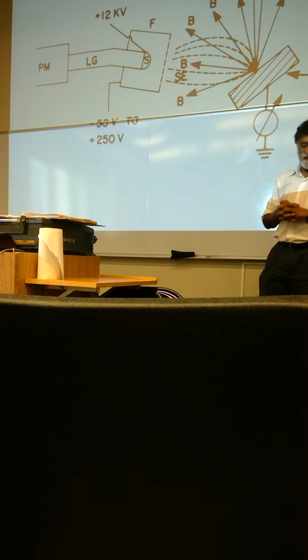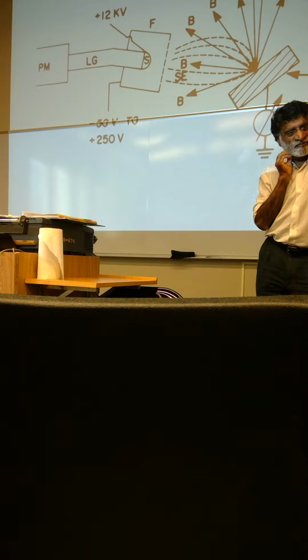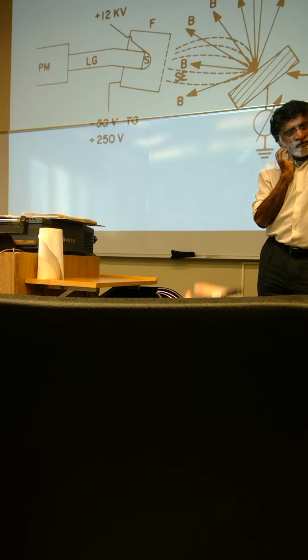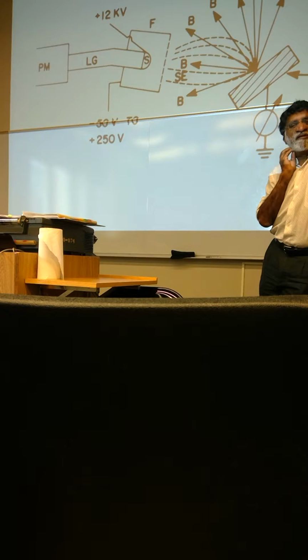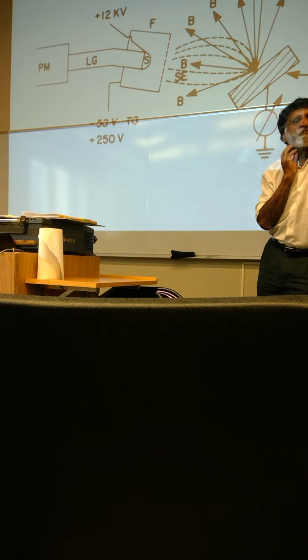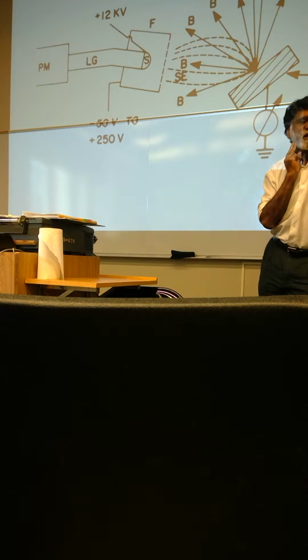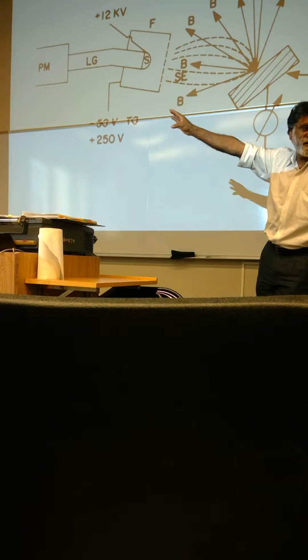Can I ask you a question? Yes, of course, please. Okay, so you've got varying energies of electrons that are hitting the scintillator. So how does it convert it into light? Because you can't just have it excite and then emit, right? Okay, so now we're getting into details here. Basically, for each electron of a certain energy, it produces a certain number of photons. And those numbers of photons are then discriminated. There is a complicated electronic circuit that goes with this.